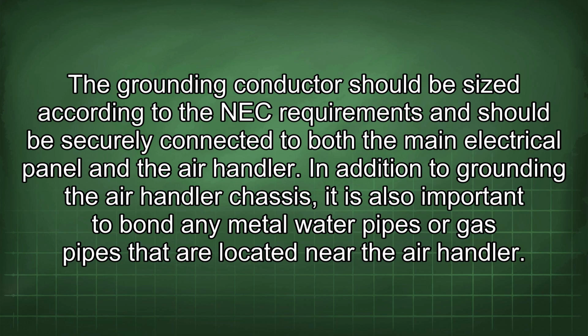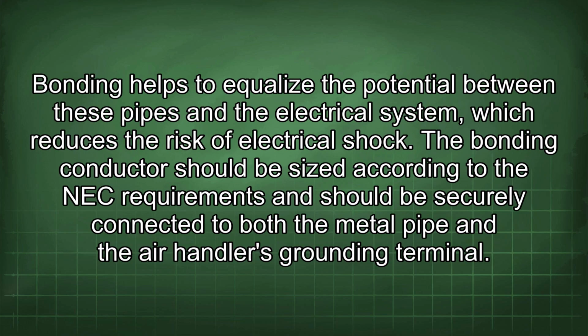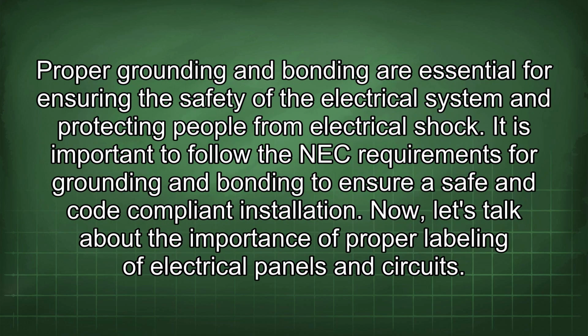In addition to grounding the air handler chassis, it is also important to bond any metal water pipes or gas pipes that are located near the air handler. Bonding helps to equalize the potential between these pipes and the electrical system, which reduces the risk of electrical shock. The bonding conductor should be sized according to the NEC requirements and should be securely connected to both the metal pipe and the air handler's grounding terminal. Proper grounding and bonding are essential for ensuring the safety of the electrical system and protecting people from electrical shock. It is important to follow the NEC requirements for grounding and bonding to ensure a safe and code-compliant installation.